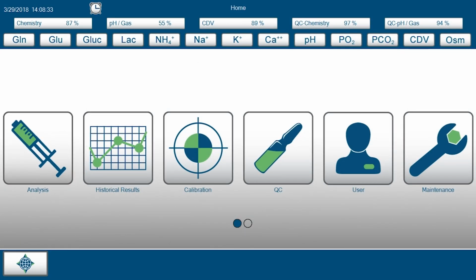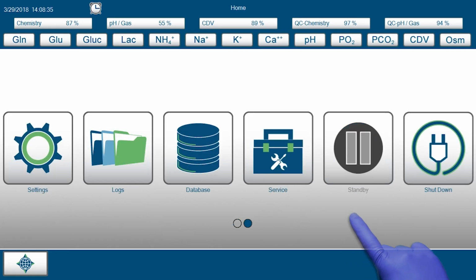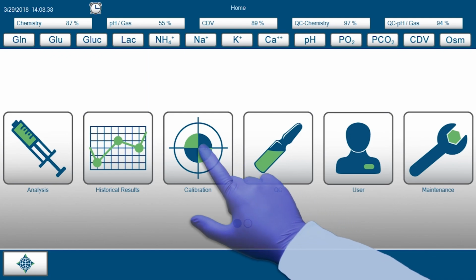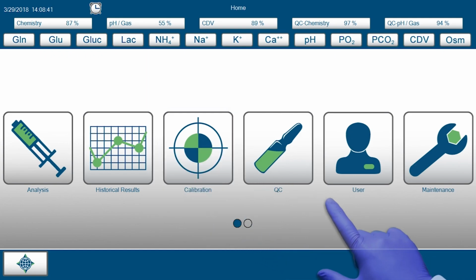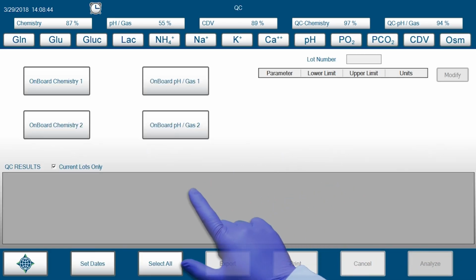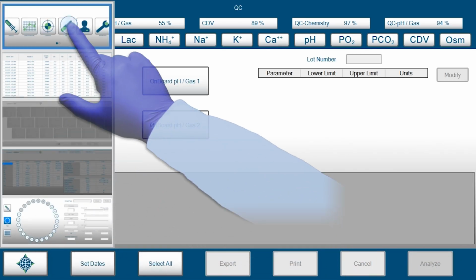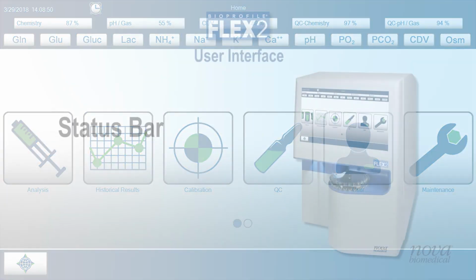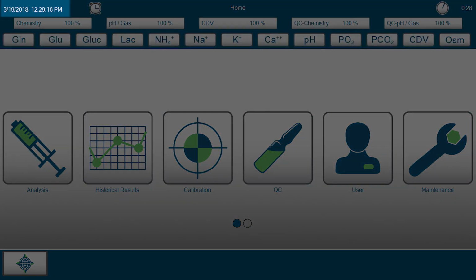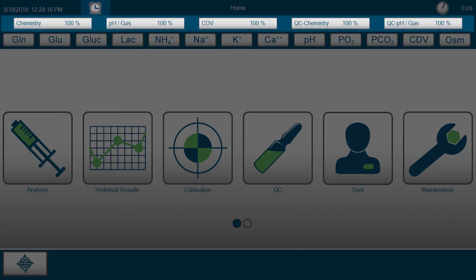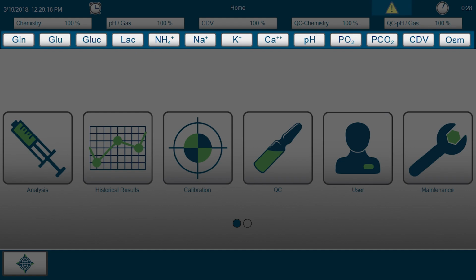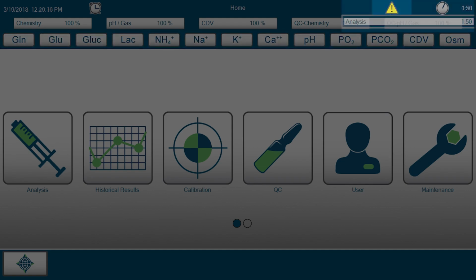You can navigate through the FLEX 2 user interface by swiping or touching different parts of the screen. The status bar is always visible at the top of the display as you navigate to different menus. In the status bar, you will find the current date and time, scheduled events icon, module status and remaining reagent volume, parameter status, alert icons when applicable, and countdown timer in the top right-hand corner when a sequence is running.